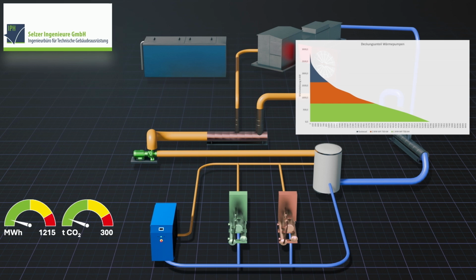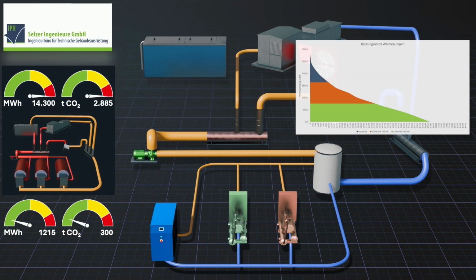Let's now compare all these results to the current conditions. Around 90% of the current gas consumption can be saved through the individual measures, the hydraulic conversion, the installation of 2 heat pumps, and the replacement of a gas boiler. That saves around 125,000 euros per year.